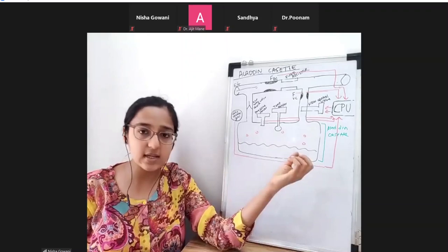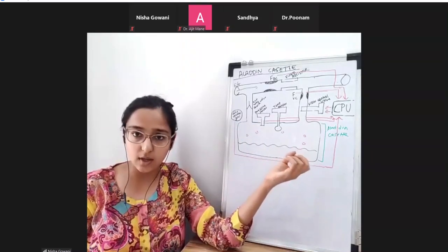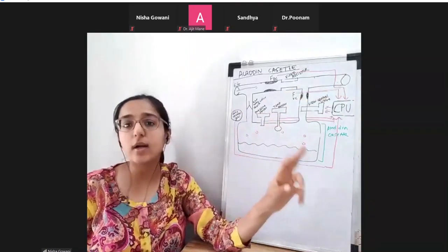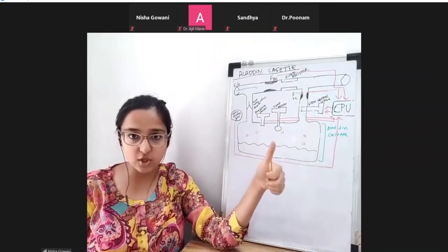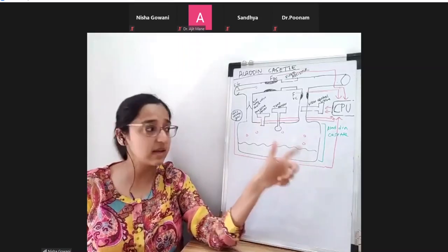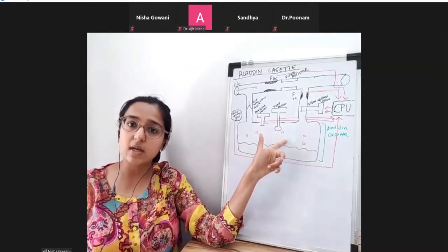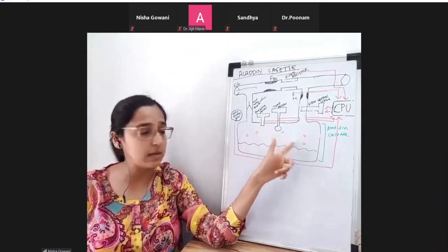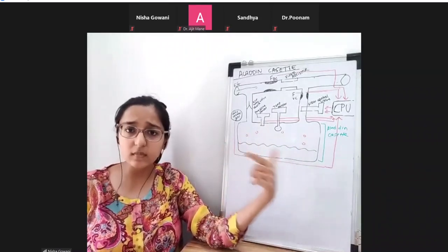This Aladdin cassette vaporizer also has the electronic ratio control, which will ensure that the oxygen concentration leaving it is not less than 25%. This is one additional safety feature. It also has a safety relief valve. This valve will open if the pressure inside exceeds roughly 1900 millimeters of mercury.